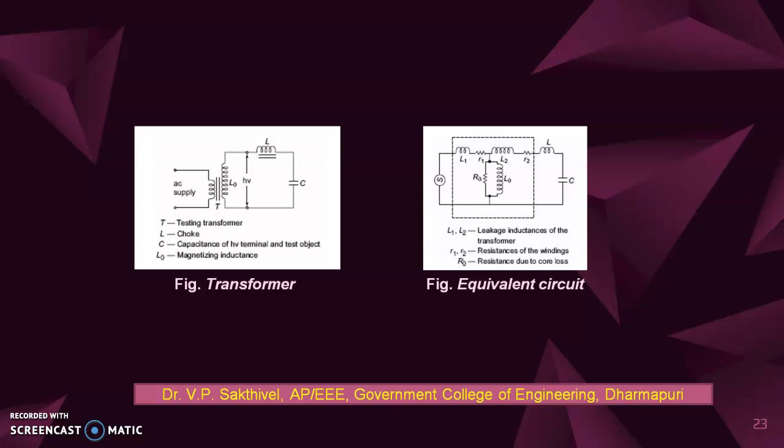If we need a 50 to 100 kV rating with a relatively large current rating, here you have to connect an inductor in addition. Under that situation, resonance occurs when ω(Le + L) = 1/(ωC), where Le is the external inductor, and L is the total equivalent leakage inductance of the transformer including its regulating transformer.